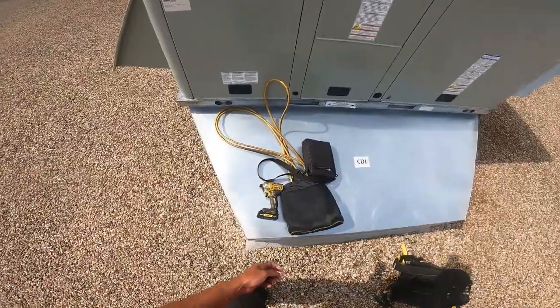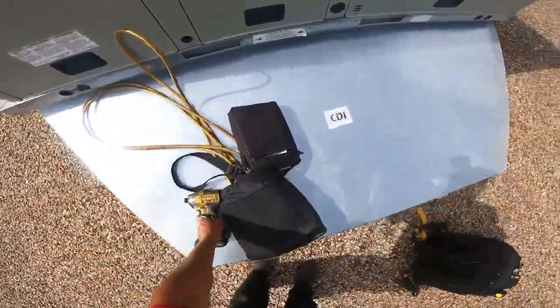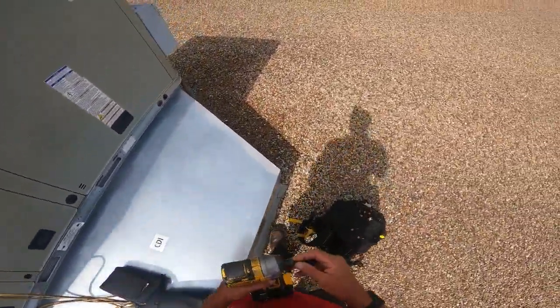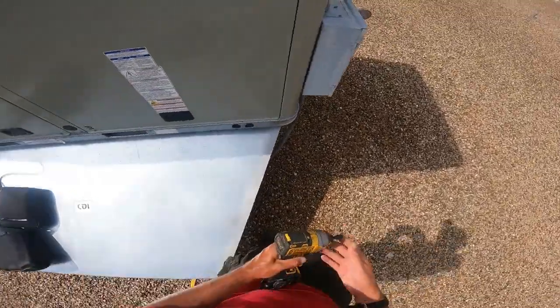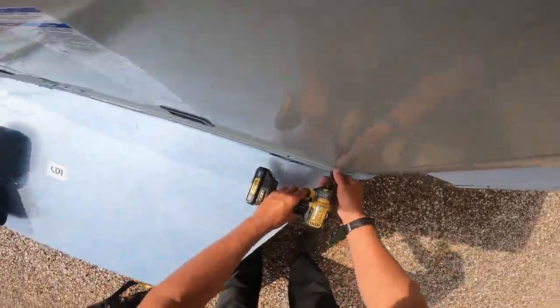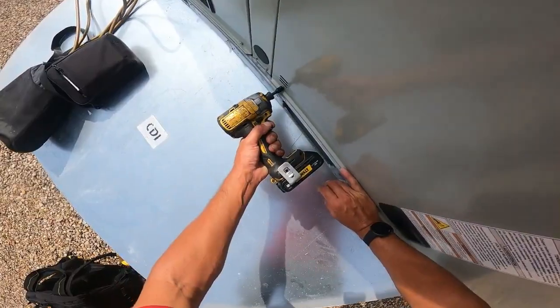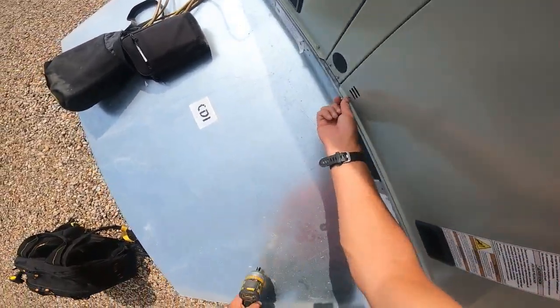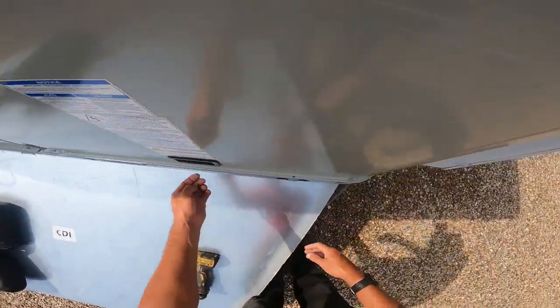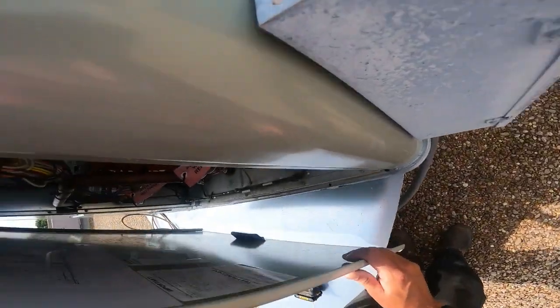All I'm gonna do is pop the filter box open, pop the condenser box open. I'm gonna see if the suction line's sweating. If it's sweating and the filters aren't dirty, then I'll go to the other unit. Let's see what we got here.